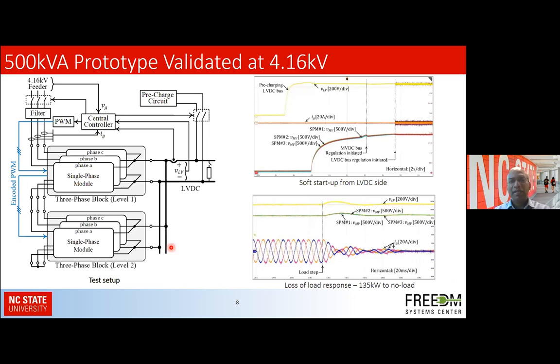So with that startup algorithm showing an experimental result here, like the pre-charging of the low voltage DC bus, then in sequence it goes into building up the medium voltage bus, and then you can see how they are uniformly maintained through controls of the DAB stage from the medium voltage bus. And then when the low voltage bus regulation is initiated, they are all having the same medium voltage, even though you are not actively controlling it from the front end of the system, or there is no communication between the DFE units for maintaining the medium voltage bus at each module.